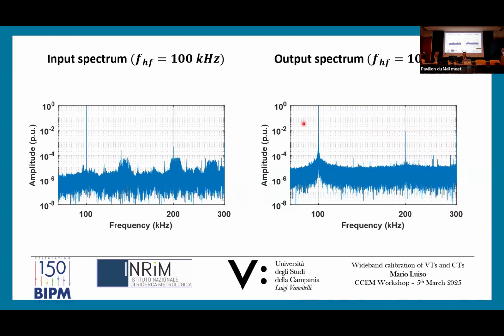This setup was used to test, for instance, a commercial medium voltage inductive transformer. In these two pictures, we can see on the left the spectrum of the input of the inductive transformer, and on the right the output. We can see that we supply almost a pure tone at 100 kilohertz, but at the output we don't have a pure tone at 100 kilohertz. So this is a proof of the non-linearity of the inductive voltage transformer even at such a high frequency value.